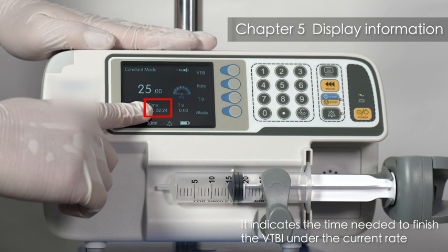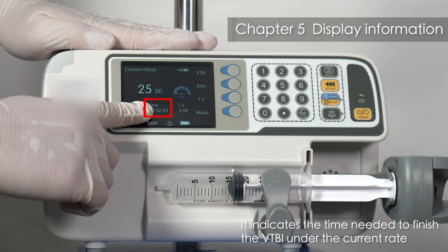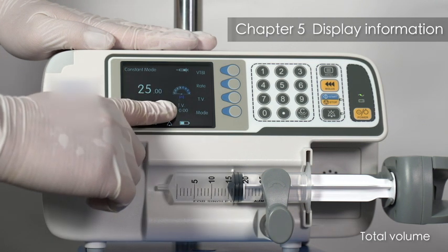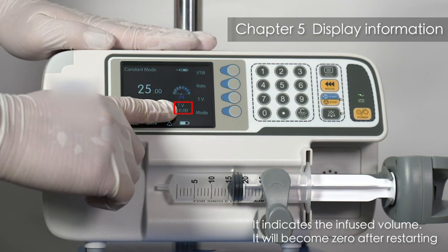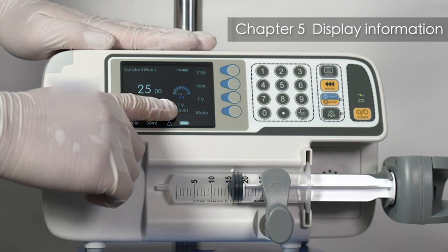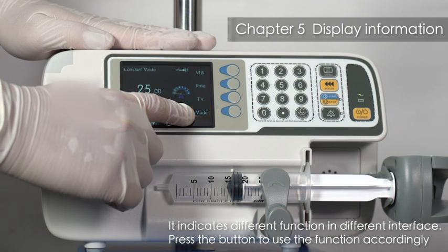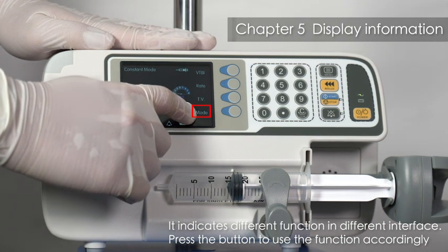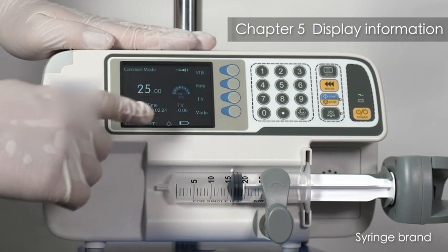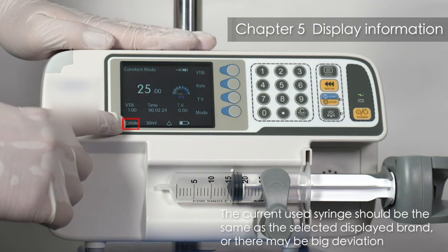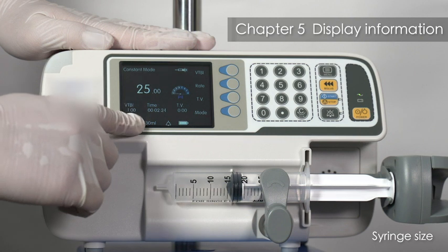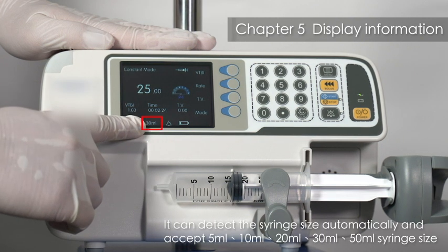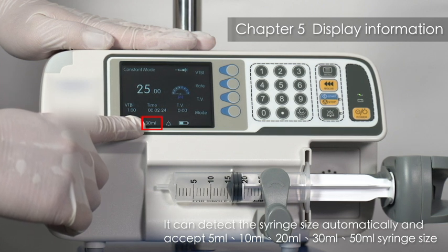Time. It indicates the time needed to finish the VTBI under the current rate. Total volume. It indicates the infused volume. It will become 0 after restarting. Function button. It indicates different function in different interface. Press the button to use the function accordingly. Syringe brand. The current used syringe should be the same as the selected display brand, or there may be big deviation. Syringe size. It can detect the syringe size automatically and accept 5 ml, 10 ml, 20 ml, 30 ml, 50 ml syringe size. Mute button.